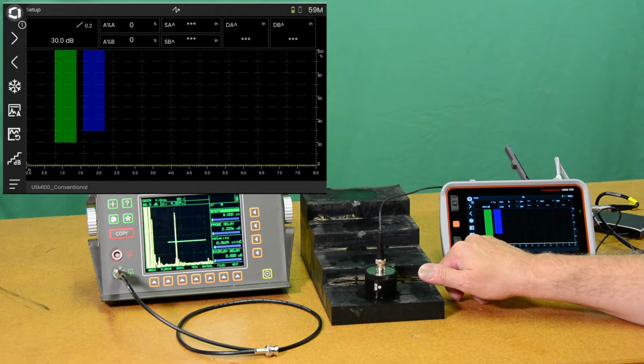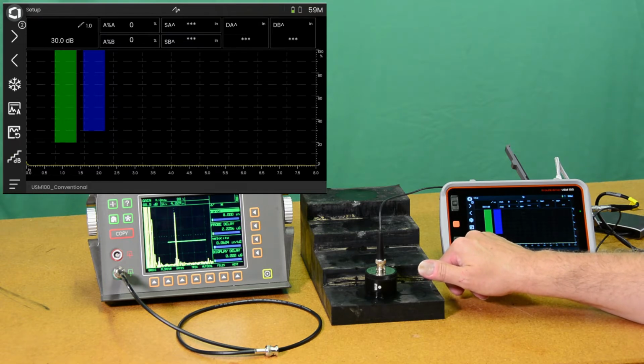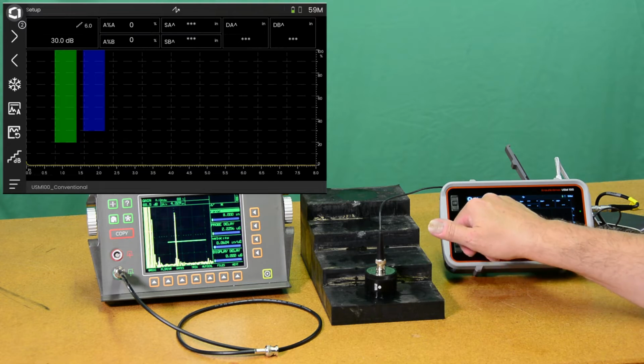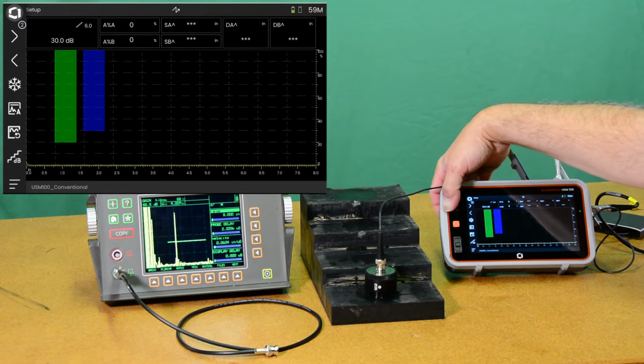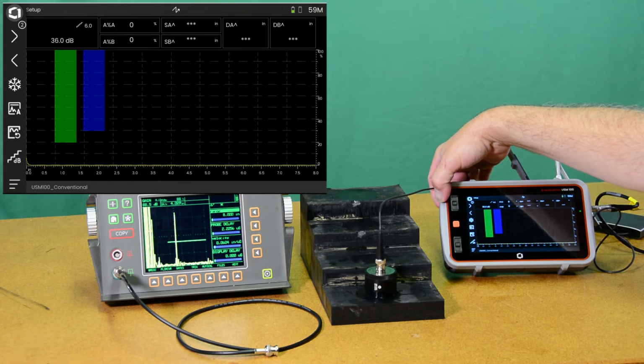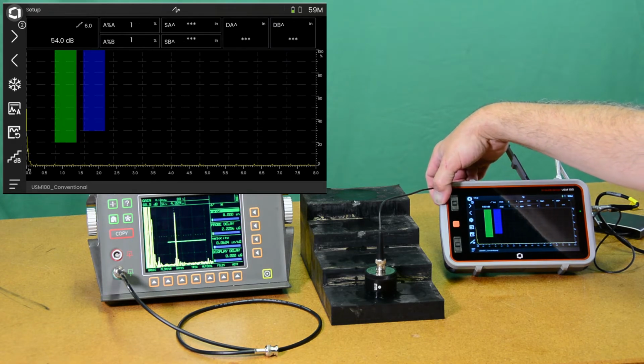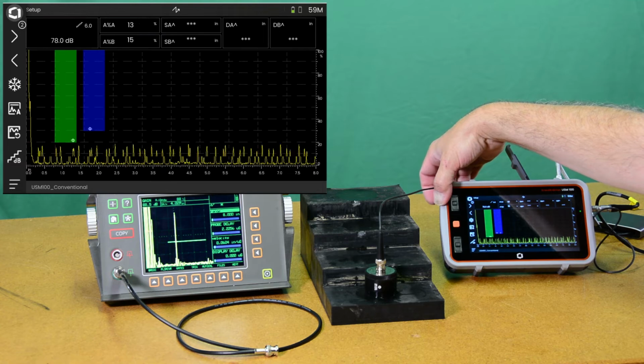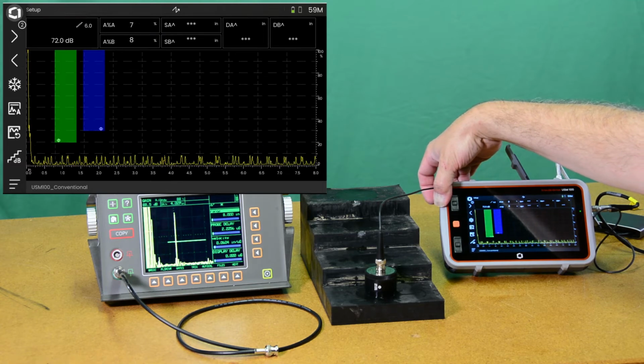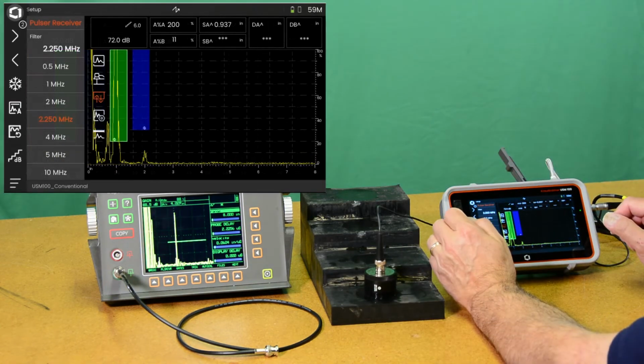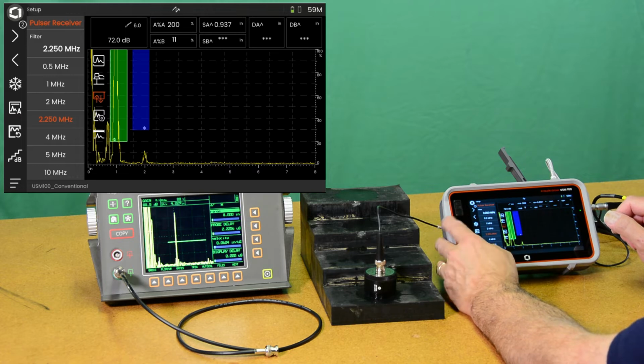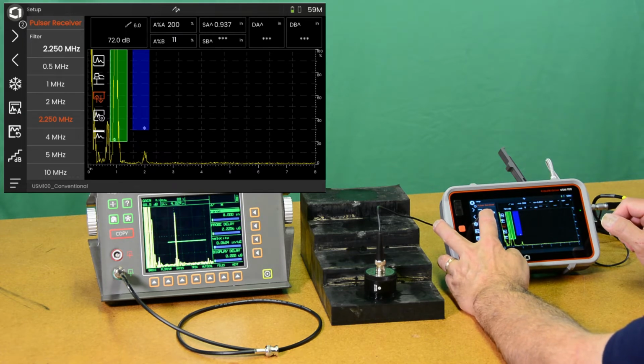Let's adjust our dB step a little bit to get some coarse gain steps. We'll take it up to 6 dB per step. And I'm going to come around the back here and hit the gain button. And we'll take that up to 70 or so. One thing we forgot to do earlier was to set it to our 0.5 megahertz filter.